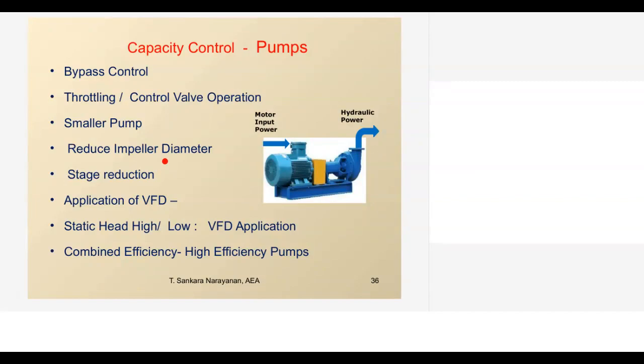So what we are telling, before finalizing VFD, you need to evaluate all these options, then go for VFD. Then static head: when it is very high, we have to review VFD application, because if you are pumping water to 35 floors, you can't suddenly reduce the pump RPM to a very low level, because it has to meet the minimum static head. So this will also put a condition on VFD application in a high head application. In low head applications, where frictional loss is there, we will get a better saving.